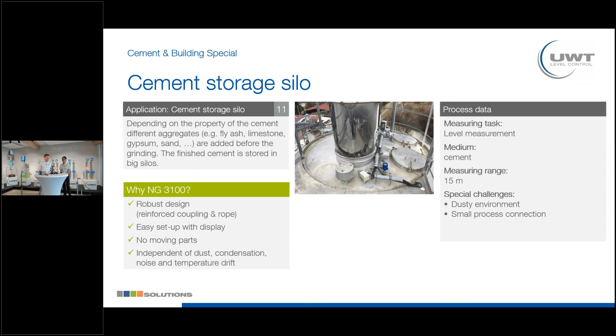It takes a little time because it's stable, but it's still quite fast. Then you have this element, and you can screw in a rope version, enter the new length, and the new length can be calibrated automatically with one push button in the menu - the sensor automatically measures the new length.